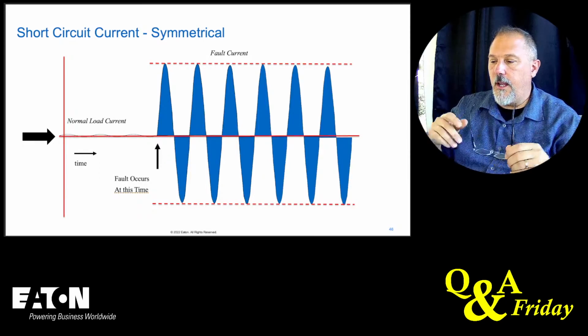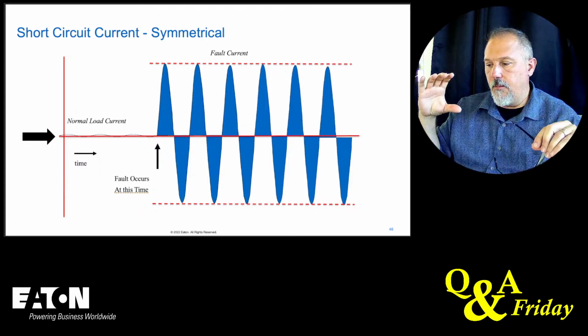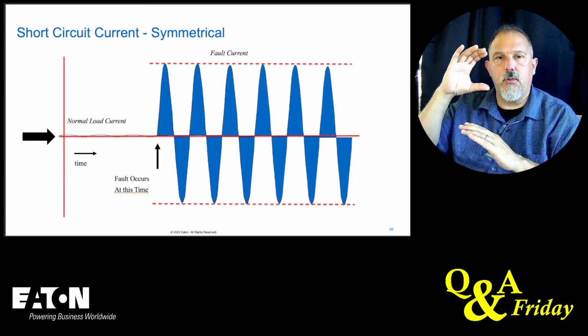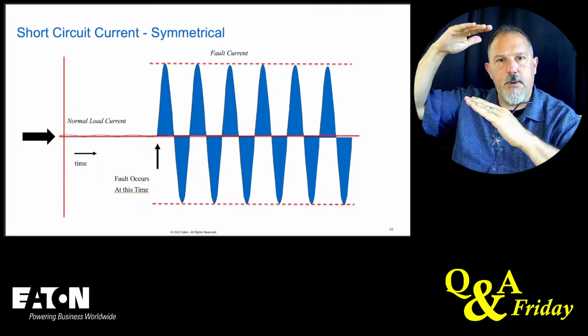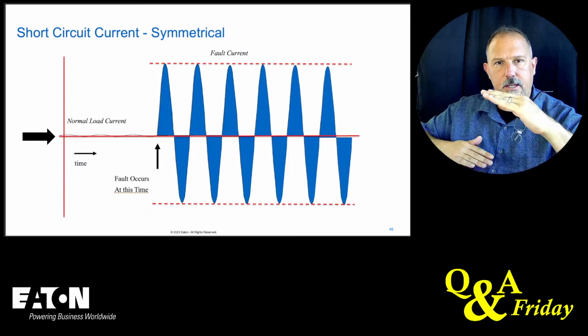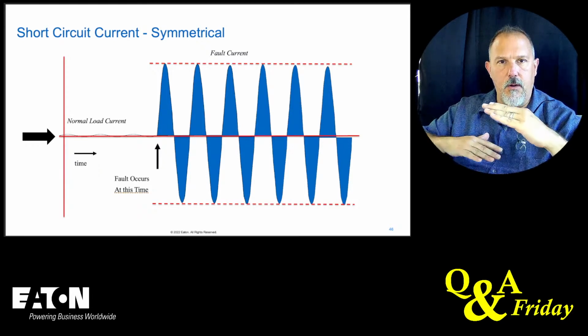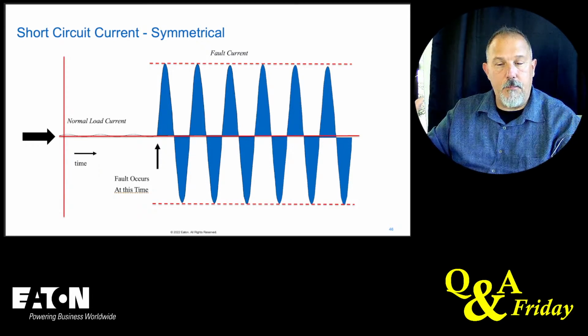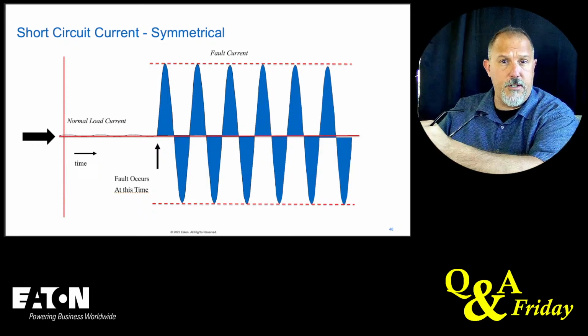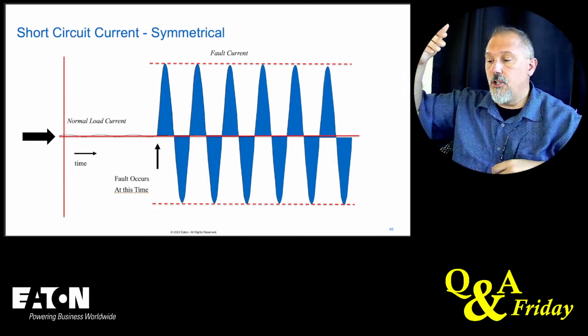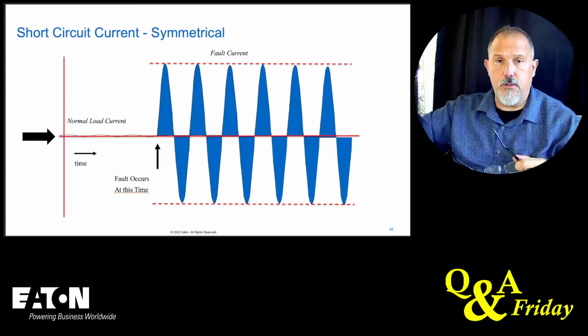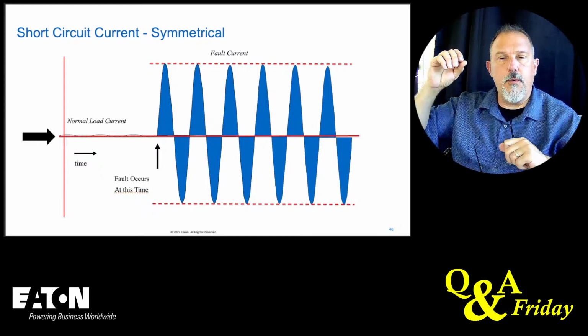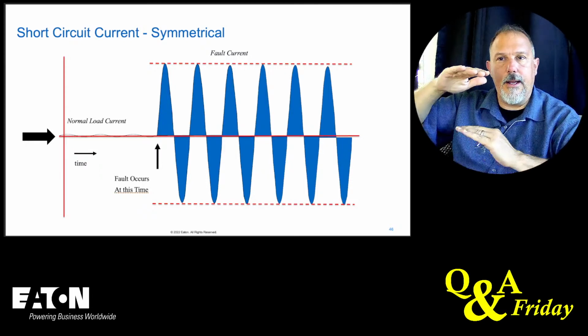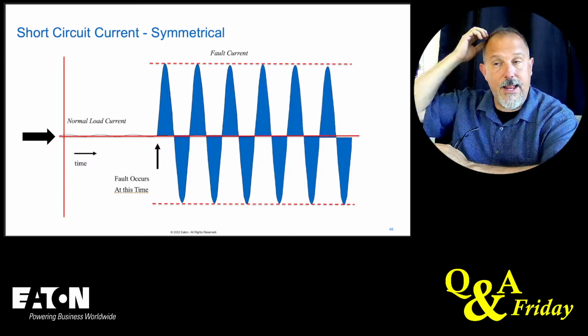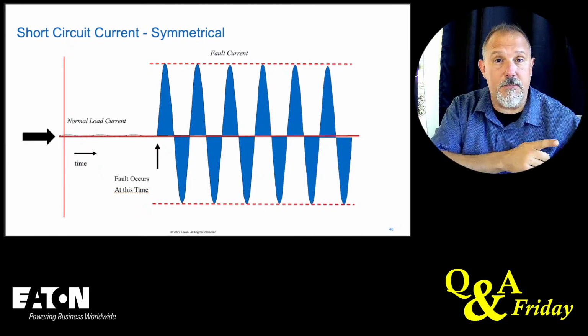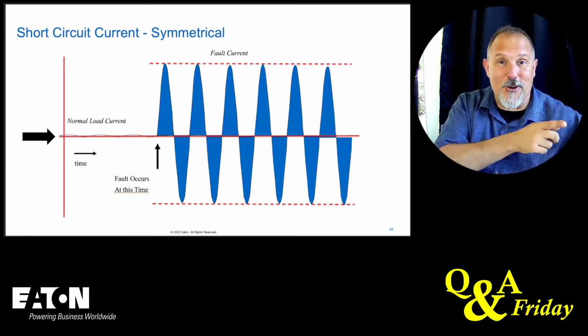So in a short circuit current, you calculate symmetrical current. The humps above are exactly the same as the size of the humps below. But that's not reality, right? But this is what we calculate as engineers. We calculate short circuit current values based on a symmetrical current, and then we pick the interrupting ratings based upon a symmetrical current value.